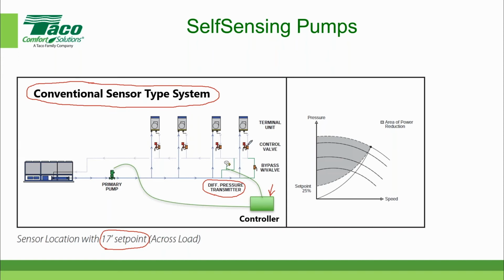Now, as the valves begin to modulate closed, the differential pressure transmitter sees an increase in pressure, and the controller says again, hey, wait a minute, I'm no longer at 17 feet. I need to slow the pump down, so I'm going to send a signal over this wire and tell the pump to slow down. That's how a conventional sensor type system works.